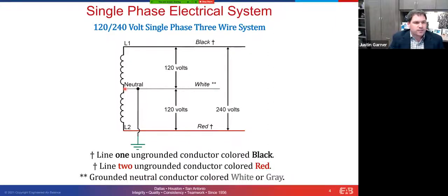Which is obviously very different than a three-phase system that we're going to talk about next. But in this type of system, which, as I said before, you would primarily find in residential or light commercial applications, you're typically going to have 240 volts differential between the two ungrounded conductors, as we would call it.